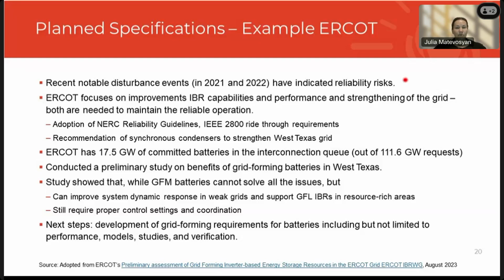And if you look at the entire interconnection queue, there are 100 gigawatts of requests in ERCOT's interconnection queues for batteries. So ERCOT is looking at whether there is any benefit of these batteries being grid forming. Some of these are going into very weak grid areas and can actually provide stability support in those areas. So they conducted a preliminary study on the benefits of grid forming batteries in West Texas, and this study showed that while these batteries cannot solve all the issues, they can improve dynamic performance of the system in the weak grid and support grid following resources that are connected there. And these are resource rich areas, so a lot of wind and solar is being built there. They still require proper control settings and coordination to operate properly and stably.